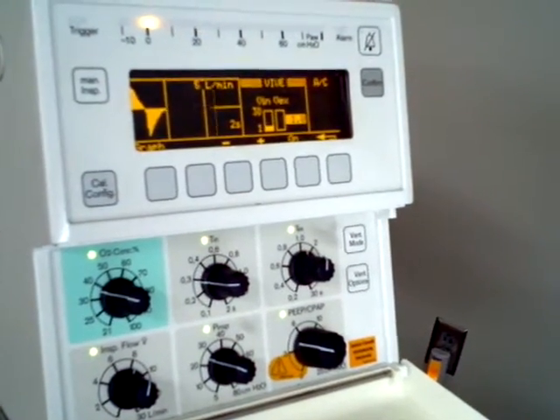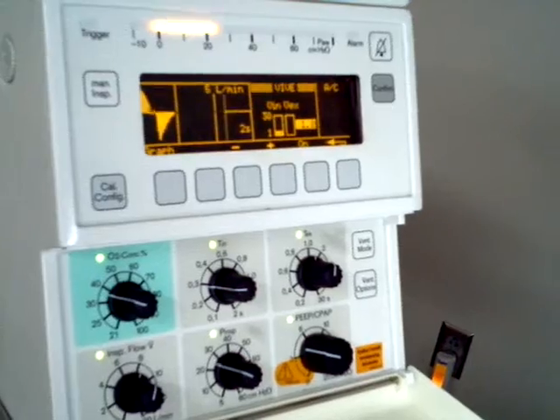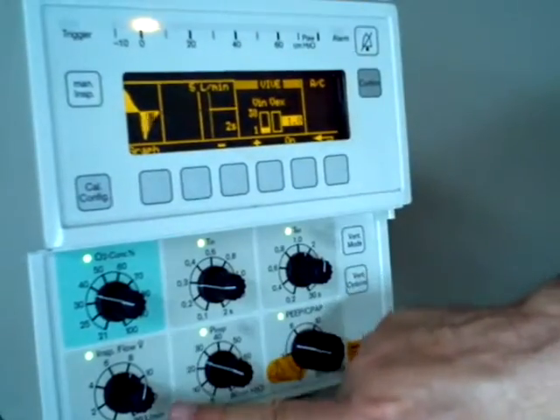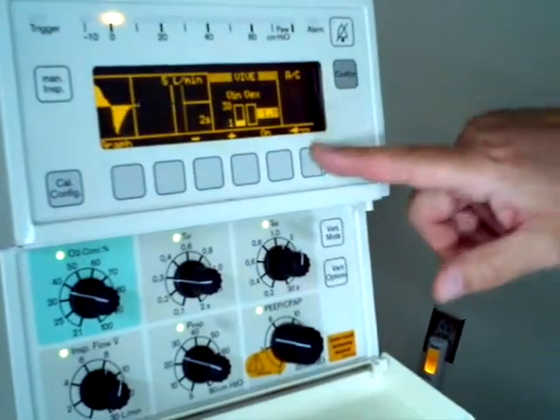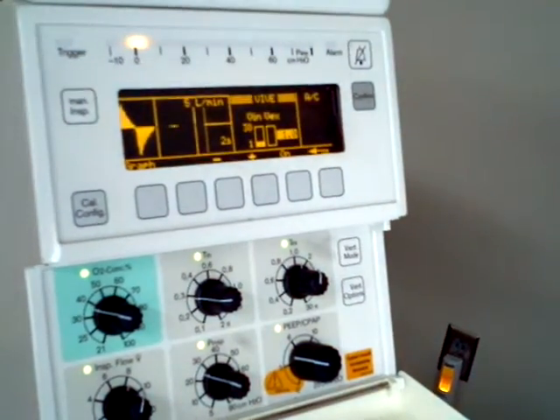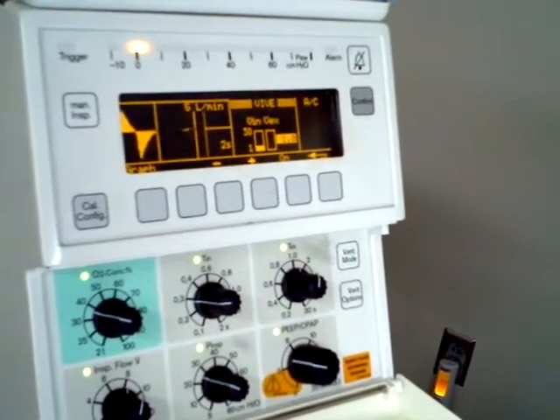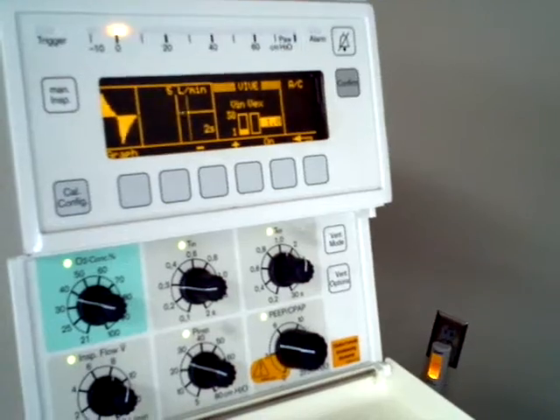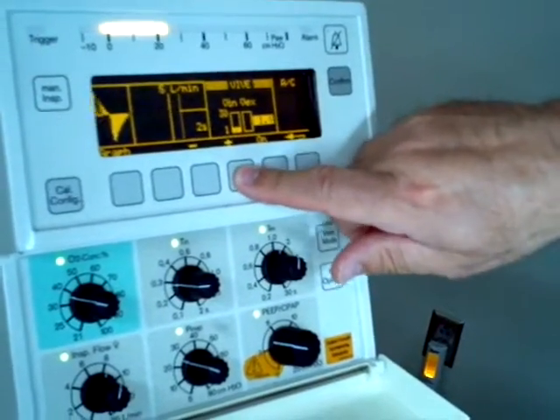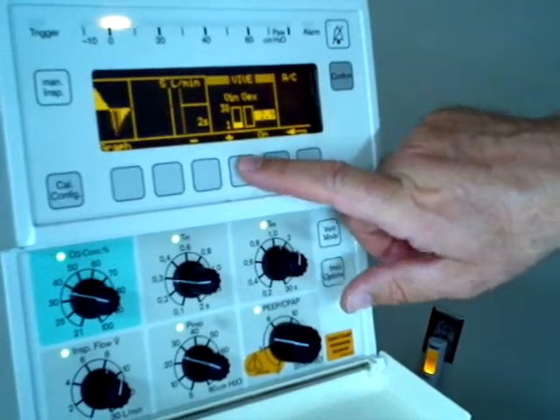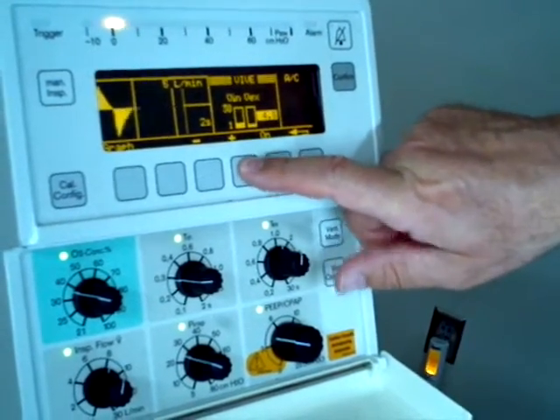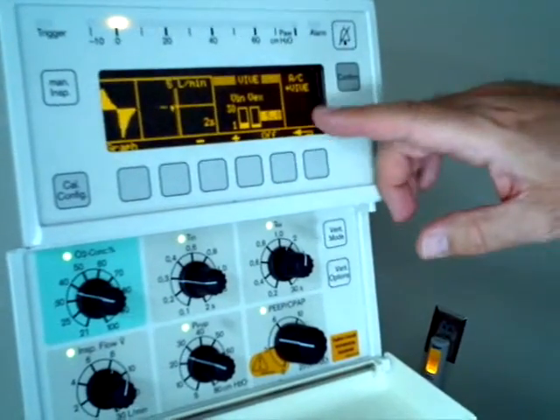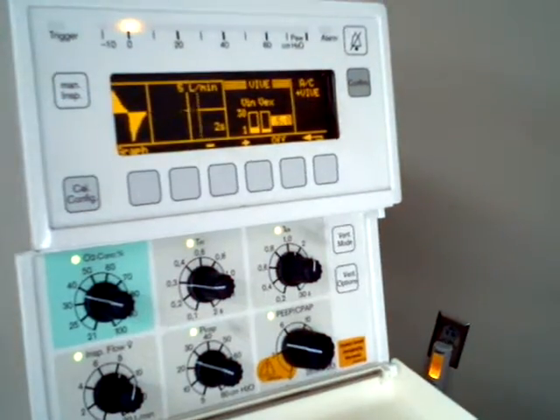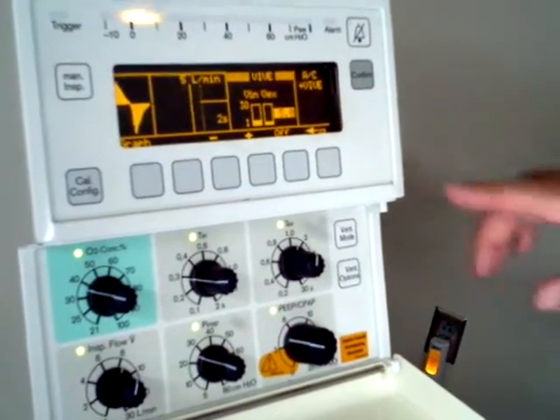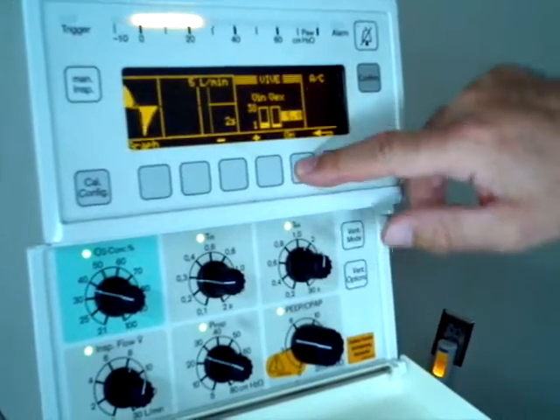Under vent options, the VIVE here actually stands for inspiratory flow, expiratory flow. You can set the expiratory flow different than the inspiratory flow. So right now our inspiratory flow is 8 liters per minute. If I activate the Vivy now, our expiratory flow will only be 1 liter per minute. In other words, the baby only has to exhale against a flow of 1 liter per minute. So I'd just say turn it to 5. It's kind of like my alarm clock. If you hold it down, it goes faster. Then you confirm it by saying that it says assist control plus VIVE. We'll talk a little bit more about that in the theory. And then I'll probably tell you to go ahead and turn it back off.